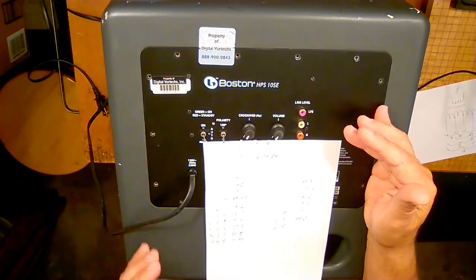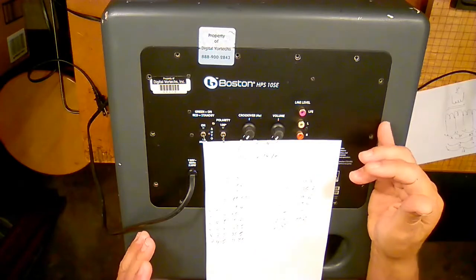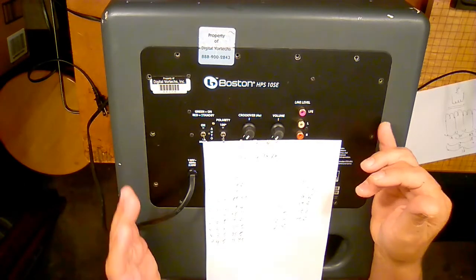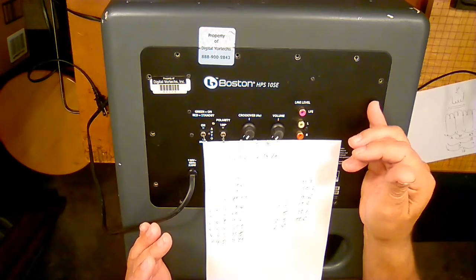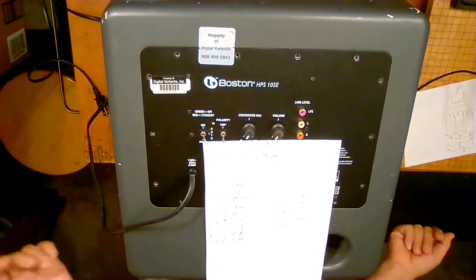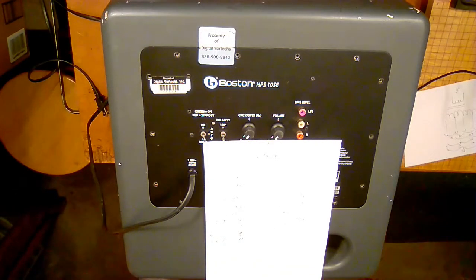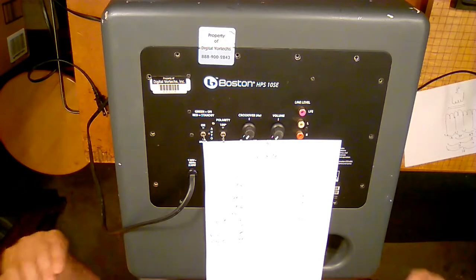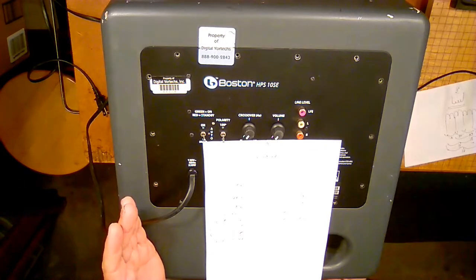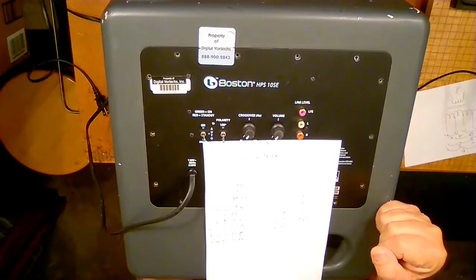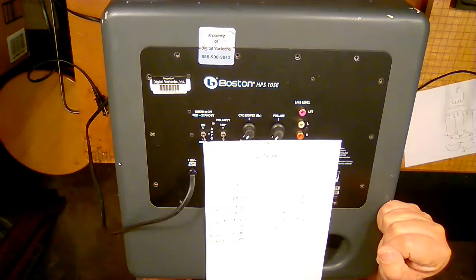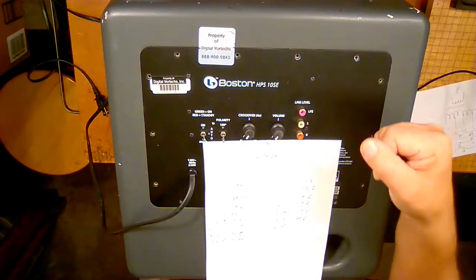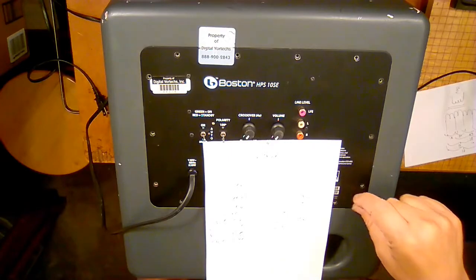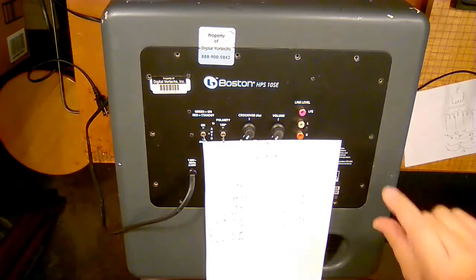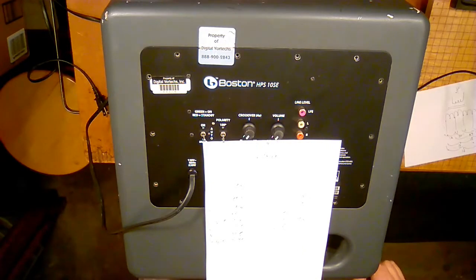That 10 turns would be a 10-to-1 ratio, so 12 volts. That 20 turns would be a 5-to-1 ratio from 100 down to 20, so 24 volts coming out of that. So you could have a 12 volt and a 24 volt. But more likely, when you want both 12 volts and 24 volts, what they do is put 100 turns on the primary, 20 turns on the secondary, with a center tap halfway through. So you've got 20 turns, but at the 10 turn point there's a little wire coming off, letting you get 12 volts and 24 volts off the same coil. This is what they call a multi-tap coil — at least that's my understanding.